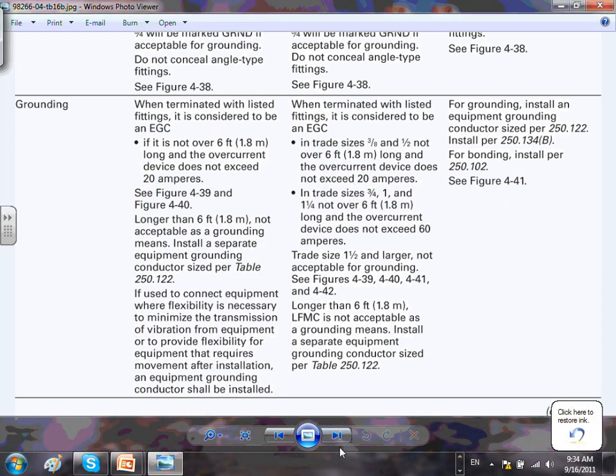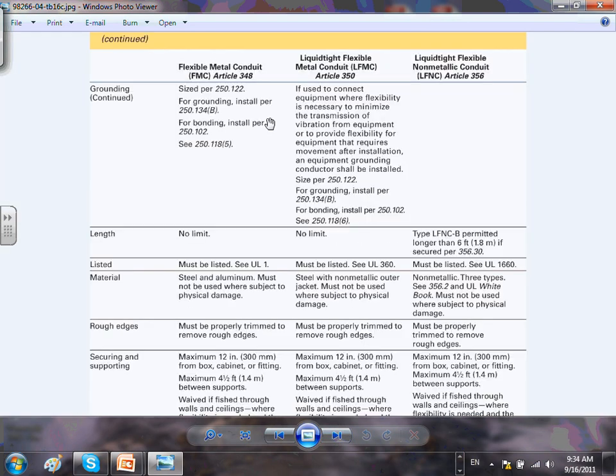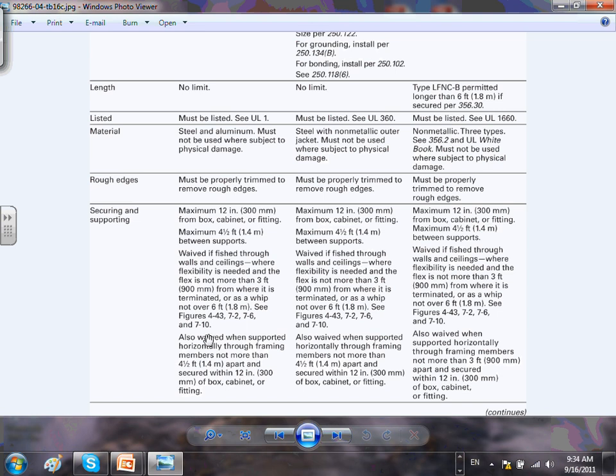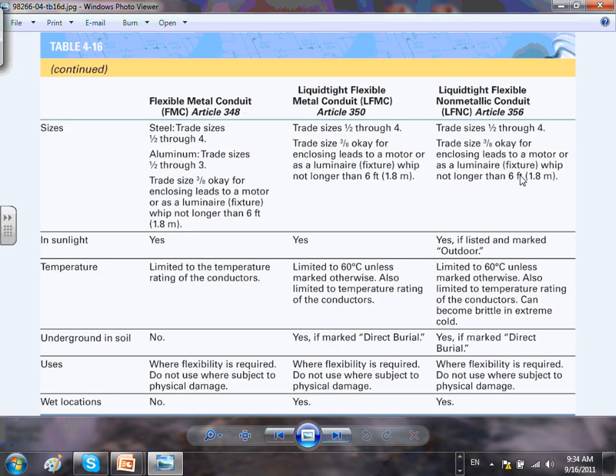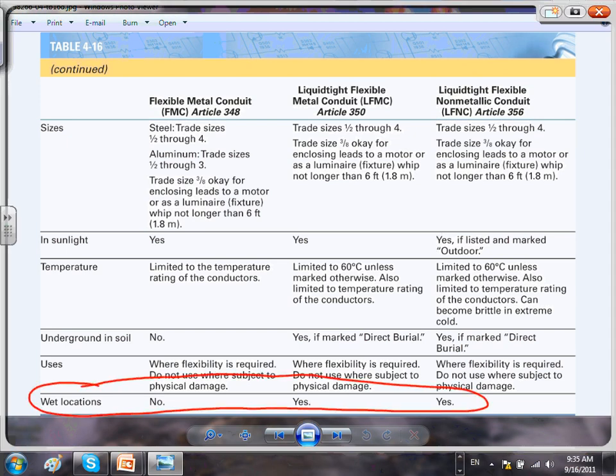The grounding for flex, listed length, and sizes — all of these come up to four inches. When we go commercial and industrial, I will make you go back to these comparison tables, because this is one of the best tables I've ever seen that compares conduit types side by side. If you want to get this information from the NEC code, it would take you at least a couple of hours pulling from every article. These tables pull all the info from all the articles side by side.